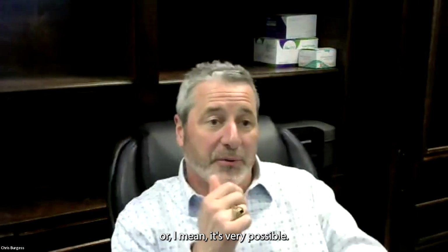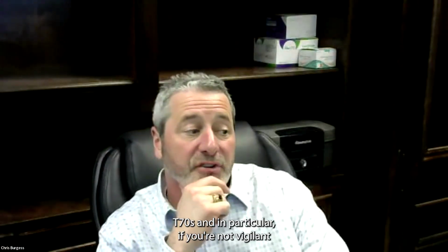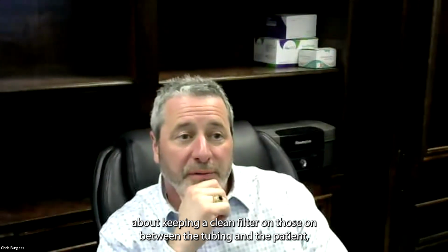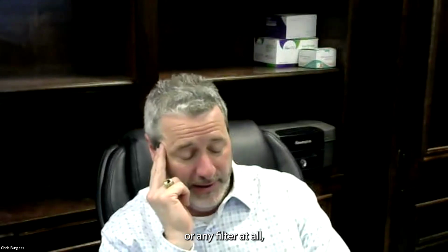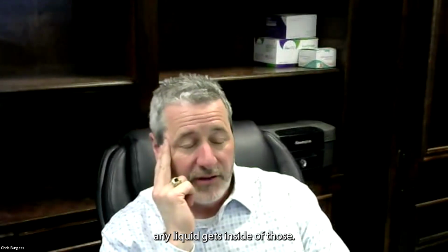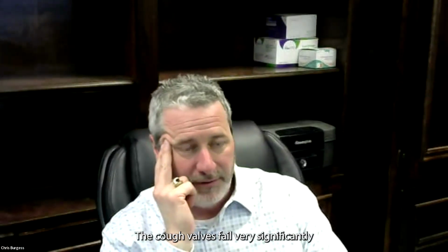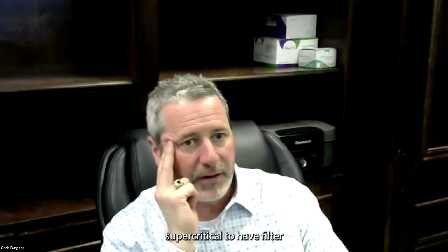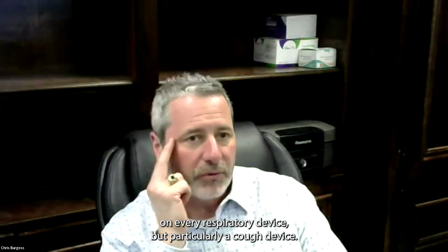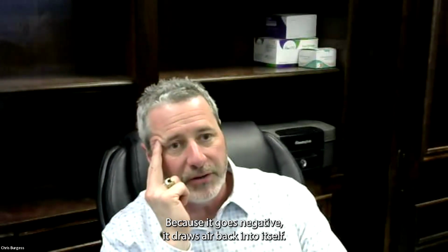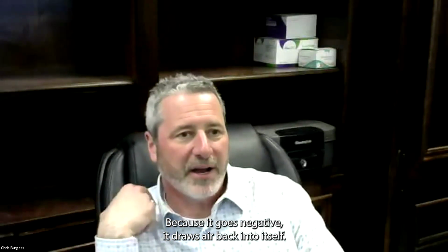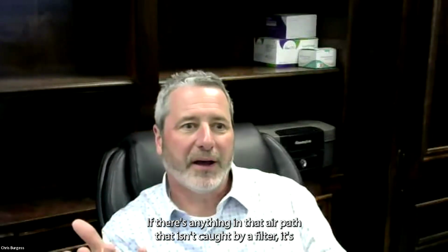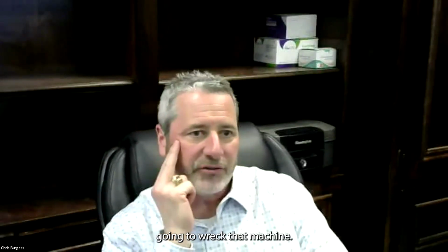Well, it's very possible. T70s in particular, if you're not vigilant about keeping a clean filter between the tubing and the patient, or any filter at all, if any liquid gets inside of those, the cough valves fail very significantly. It's super critical to have a filter on every respiratory device, but particularly a cough device, because it goes negative. It draws air back into itself. If there's anything in that air path that isn't caught by a filter, it's going to wreck that machine.